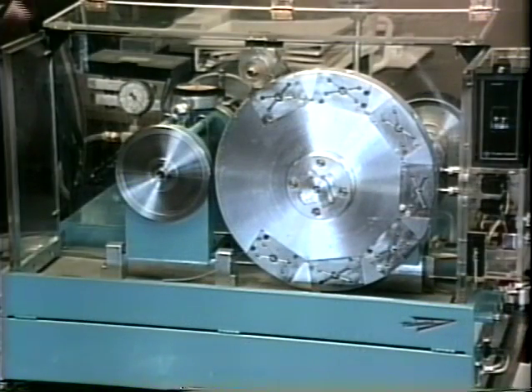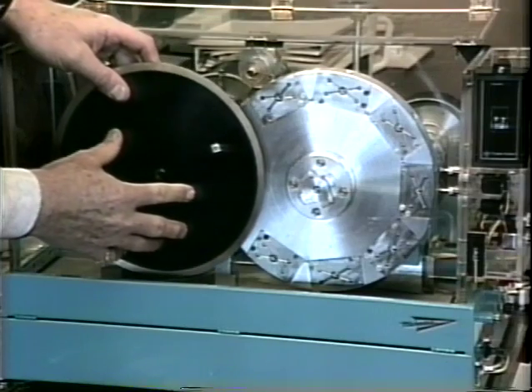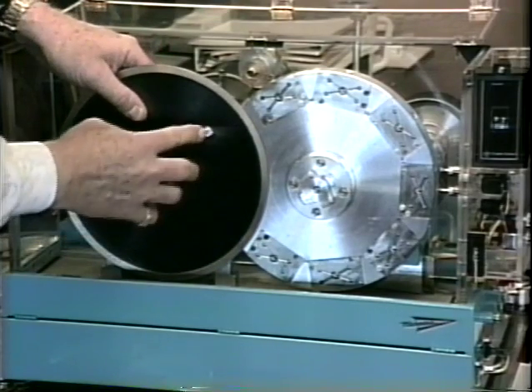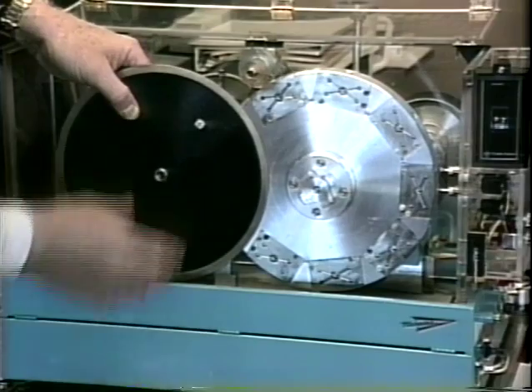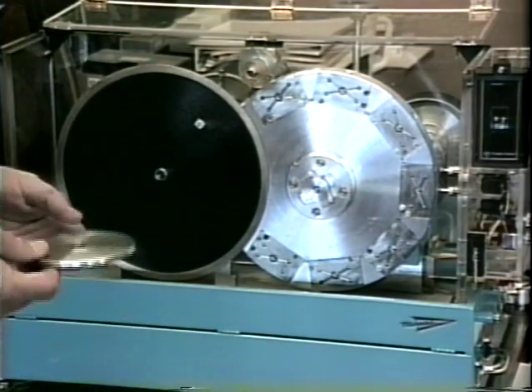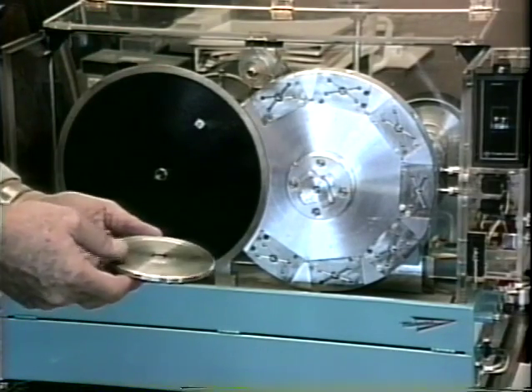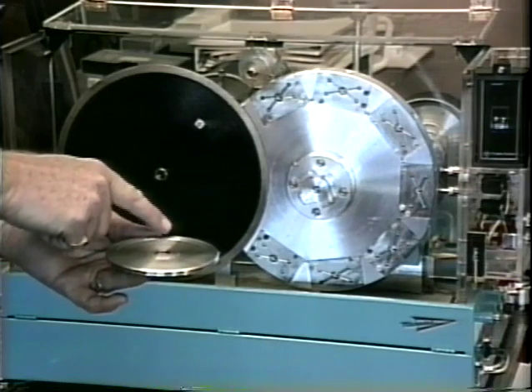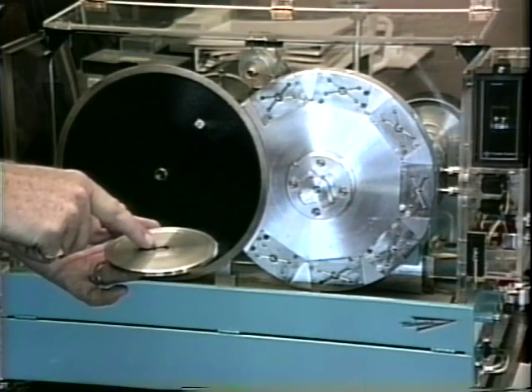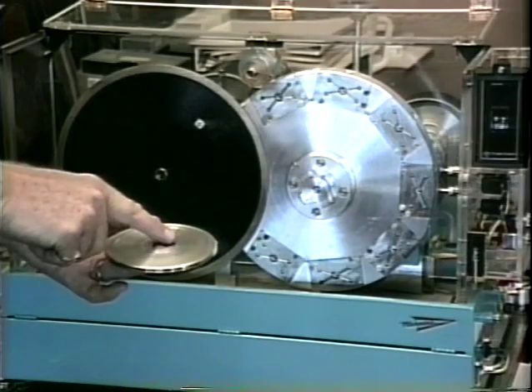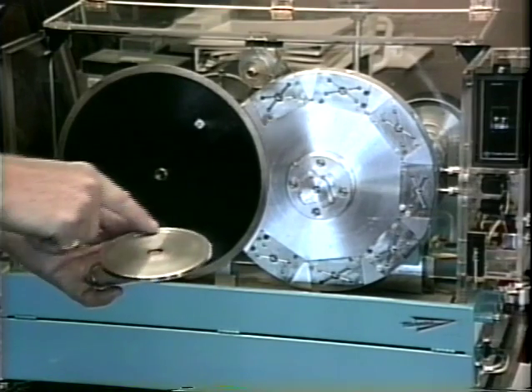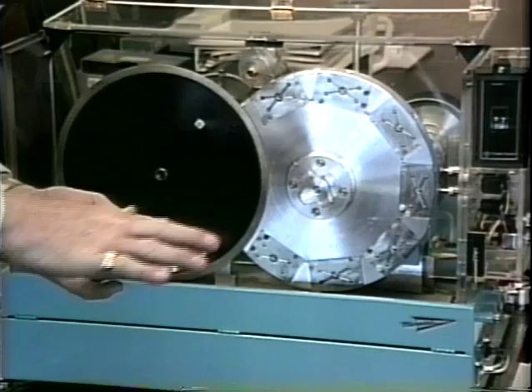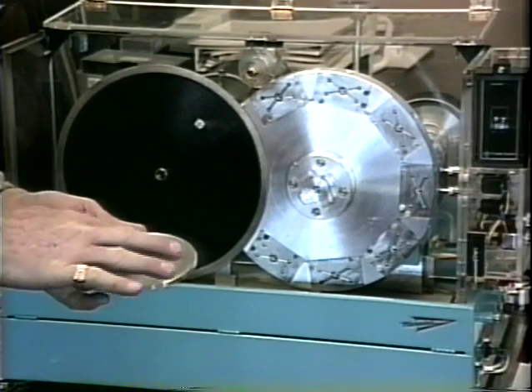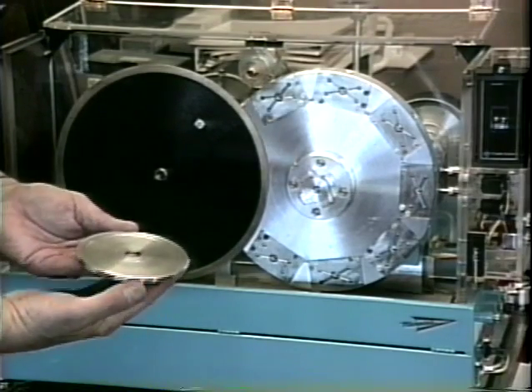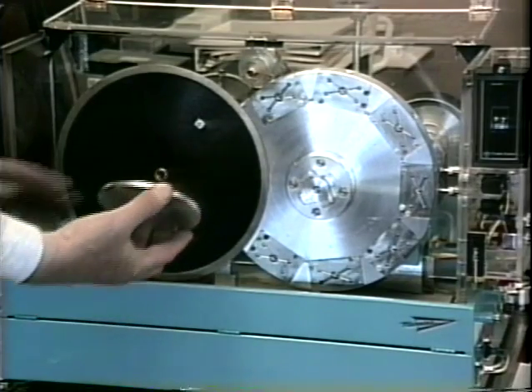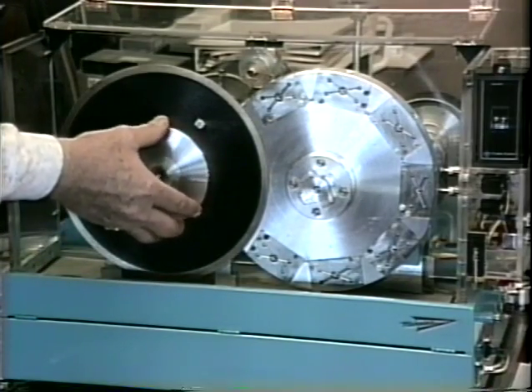To mount the diamond blade, we mount it on the spindle with the orientation mark facing out. Then we clamp it with the clamping disc. This disc has two bands, an outer band and an inner band. The inner band is relieved below the outer band a slight bit, so the outer band will tighten first, followed by the inner band. This clamping disc is placed with the bands toward the diamond plate.